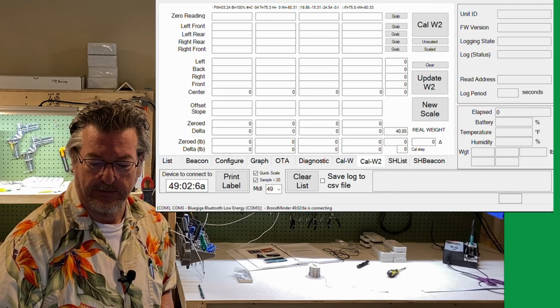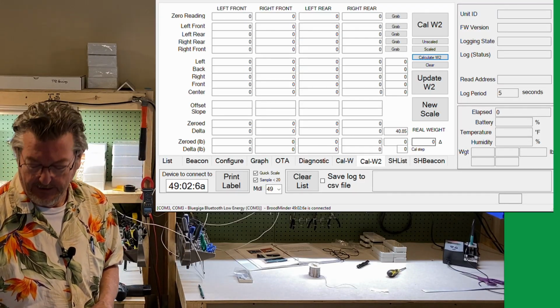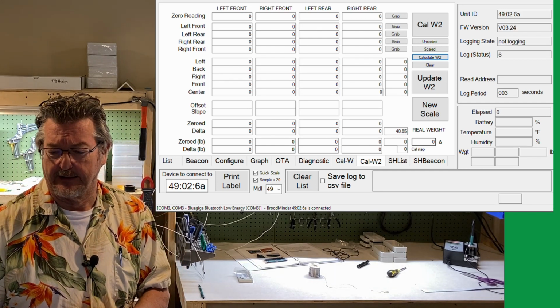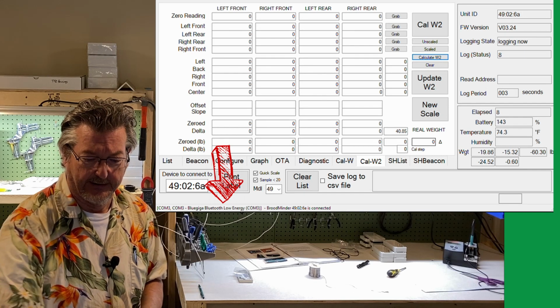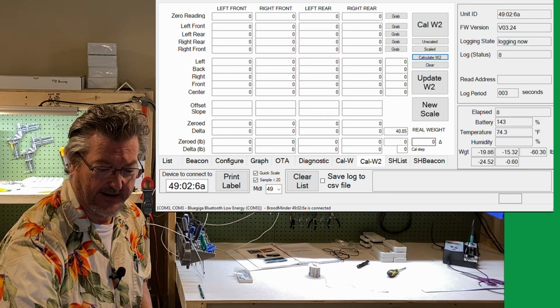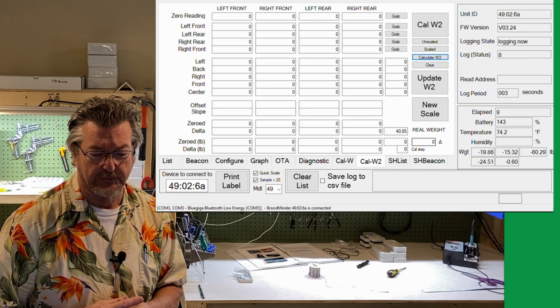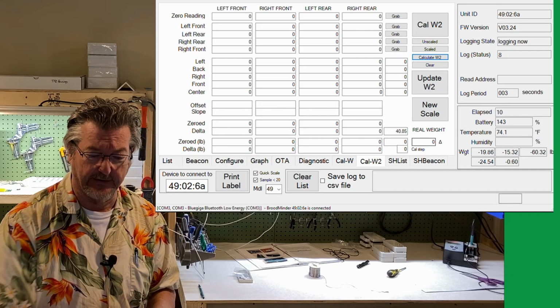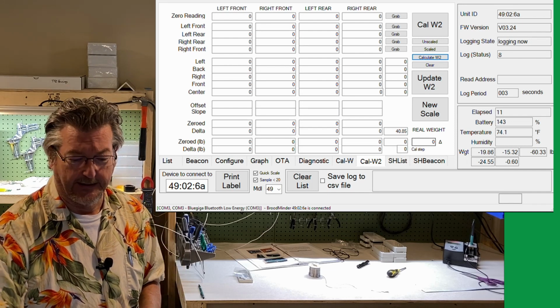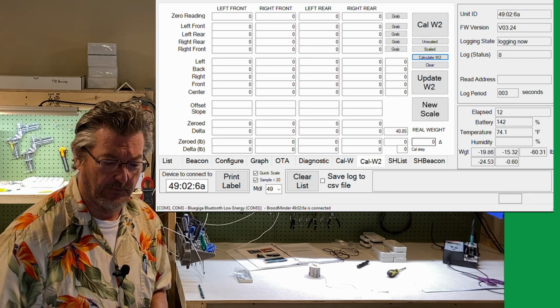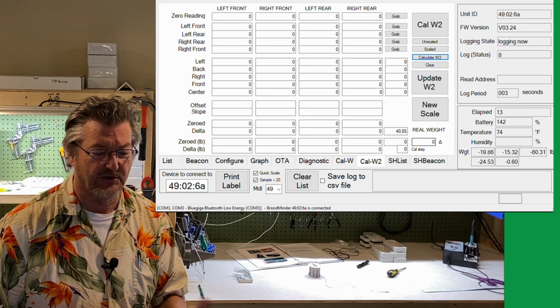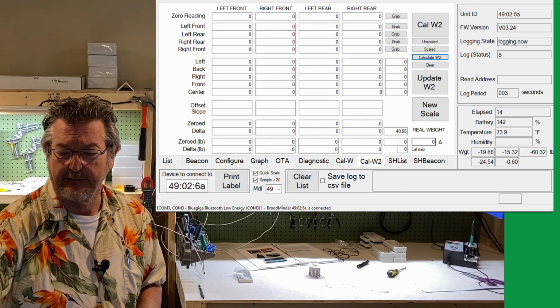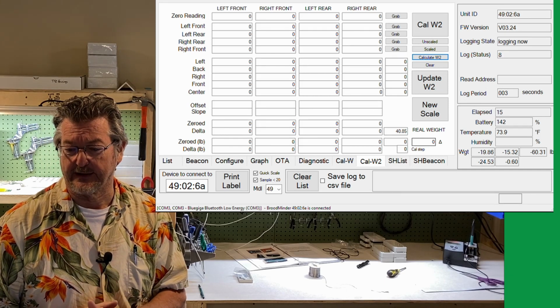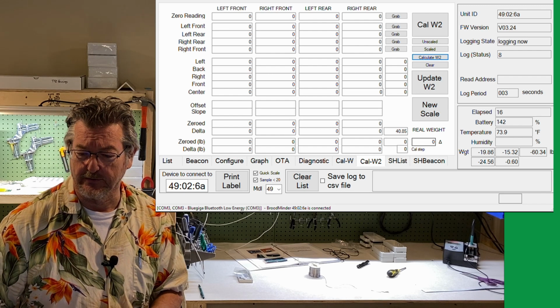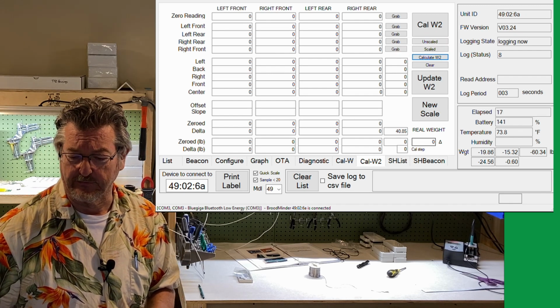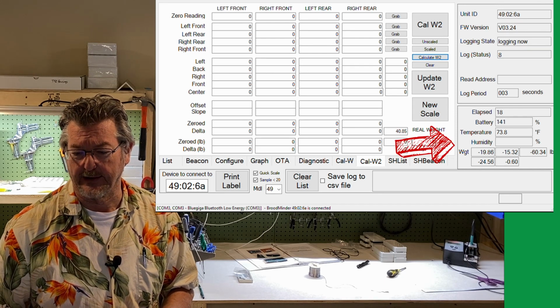Now what we'll do is go to calibrate the weight, and down here at the bottom it tells you the connection status. It tells you that it found the Bluetooth module on COM3 in this case - it looks for that automatically. Then it looks for whatever device is listed in this window, the device to connect to. Once it's connected, you'll see it give the status up here in the right-hand corner, and the values it reads down in the lower right-hand corner.